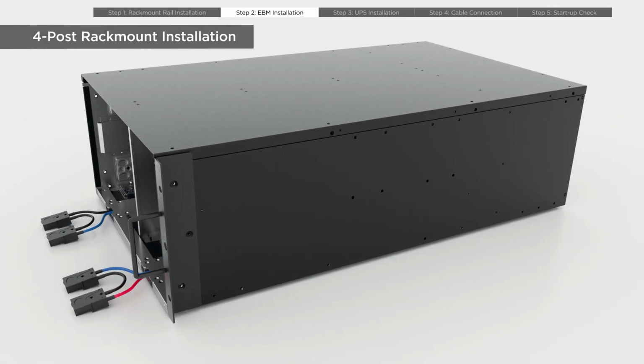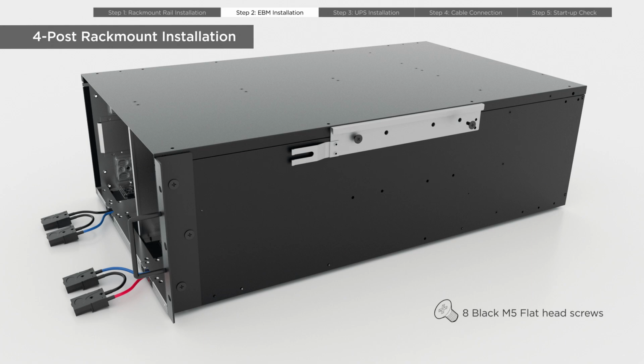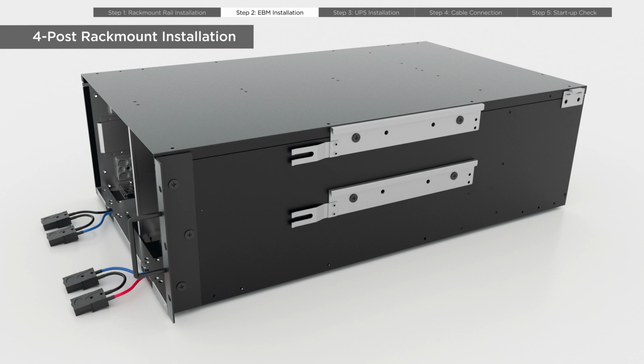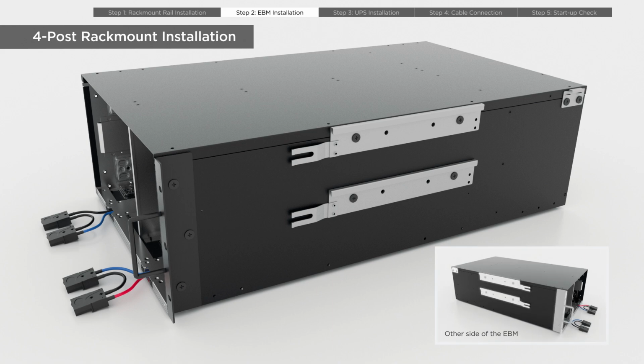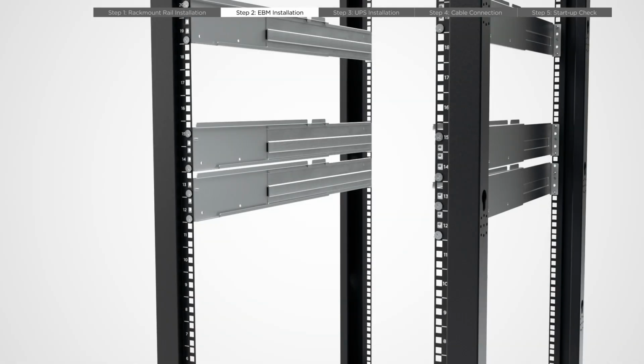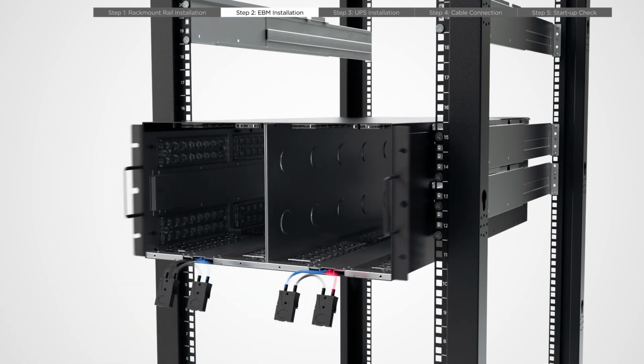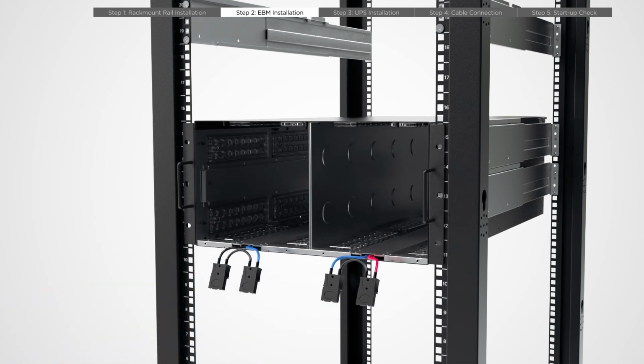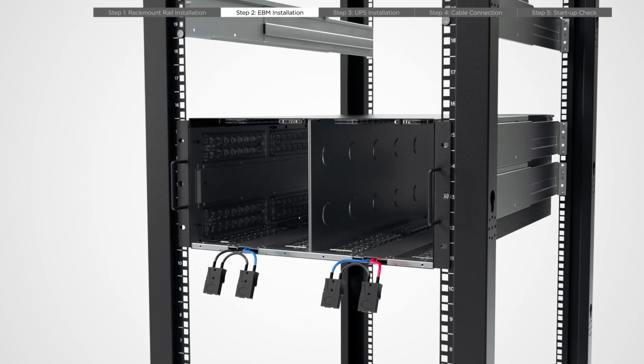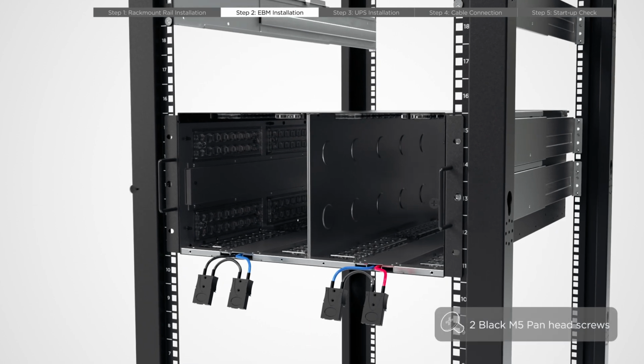Install the 2 rack mount ears onto both sides of the EBM using 3 black flat head screws on each side. Secure each hanging bracket using 2 black flat head screws, 2 hanging brackets on each side. Then install the 2 rear hanging brackets onto both sides of the EBM using 2 black flat head screws on each side. Slide the EBM hanging brackets onto the mounted rails with the battery connectors facing forward. From the front, secure the EBM to the rack with 1 black pan head screw on each side.